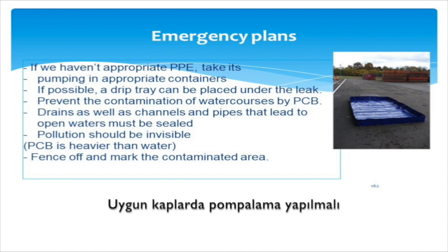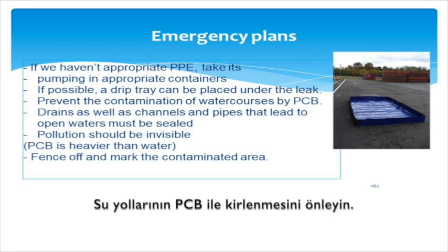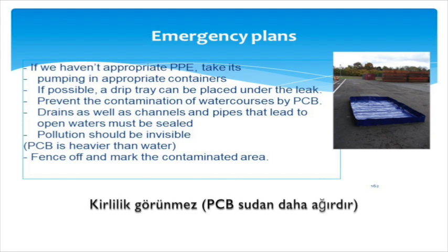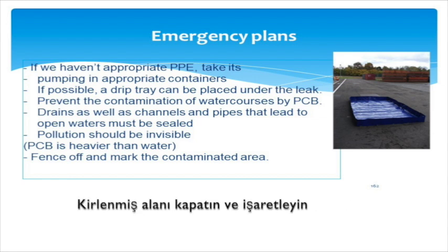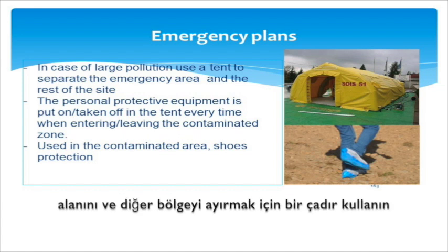Put the waste in an appropriate container. If possible, a drip tray can be placed under the leak. Prevent the contamination of watercourses by PCB. Drains as well as channels and pipes that lead to open water must be sealed. Pollution may be invisible. The PCB is heavier than water. Fence off and mark the contaminated area. In case of large pollution, use a tent to separate the emergency area from the rest of the site.